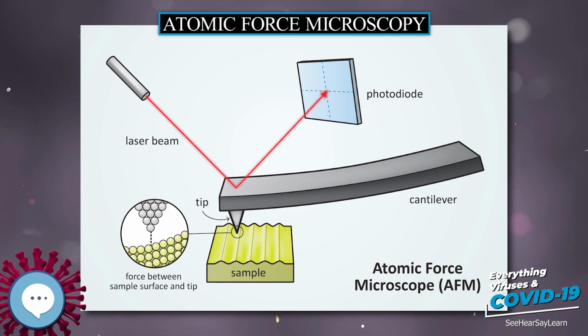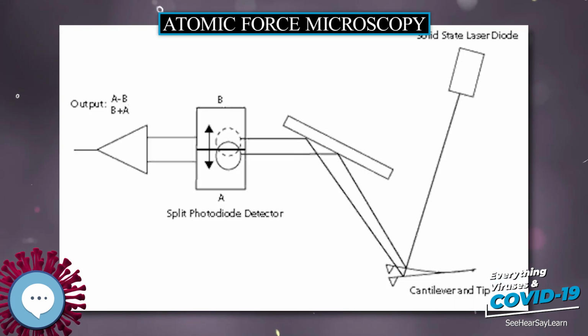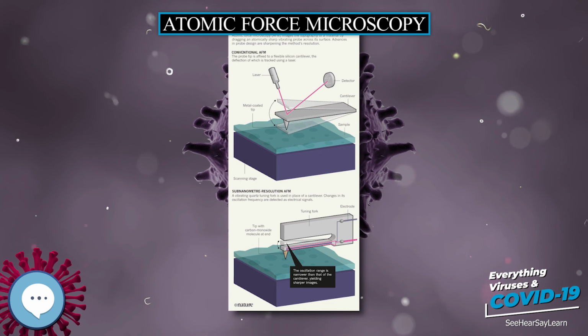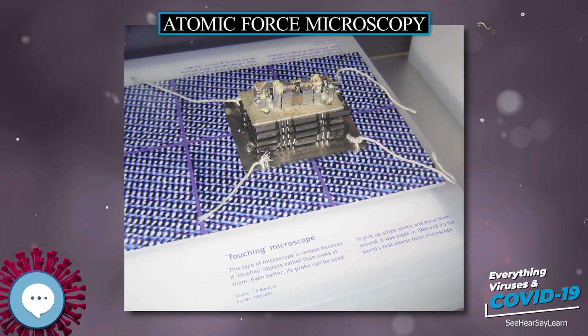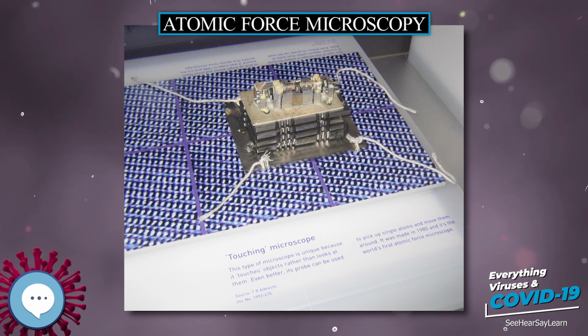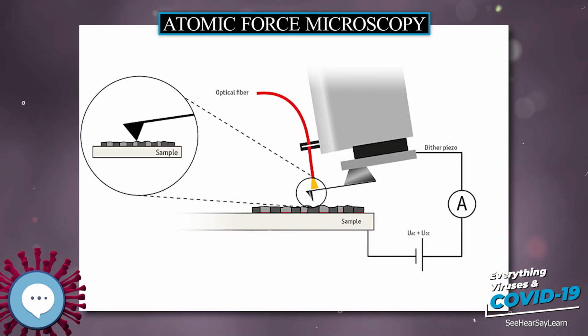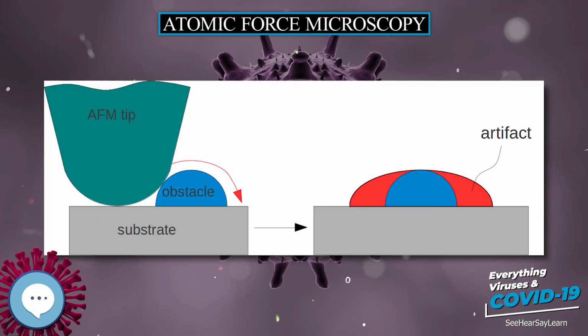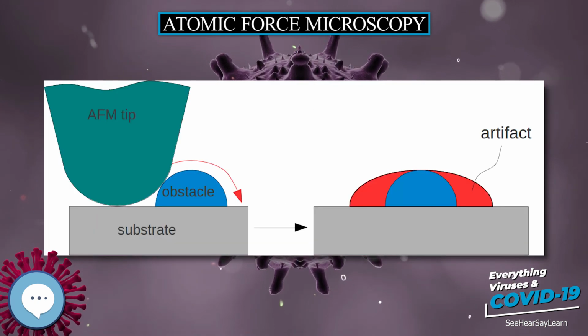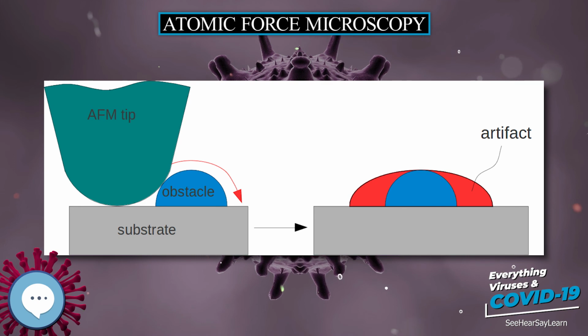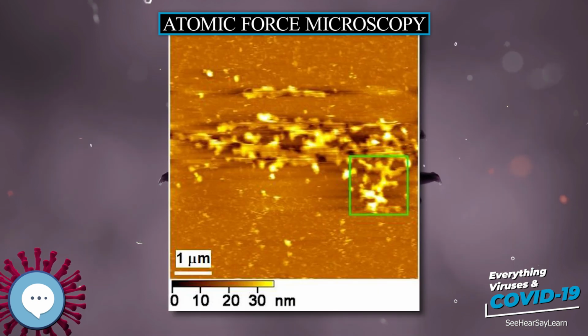The Z feedback loop controls the relative distance between the probe and the sample by outputting control signals to keep constant one of frequency, vibration and phase, which typically corresponds to the motion of the cantilever. For instance, voltage is applied to the Z piezoelectric element and it moves the sample up and down in the Z direction. Details will be explained in the case of constant dF mode, FM-AFM, among AFM as an instance, in the next section. Topographic image of FM-AFM.